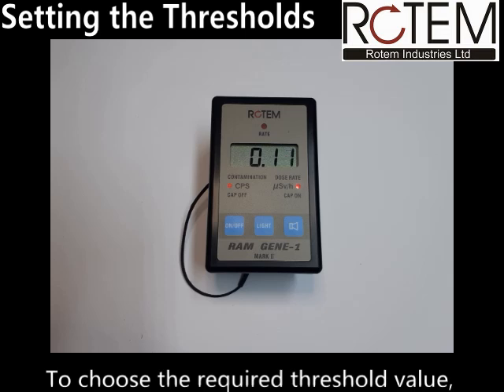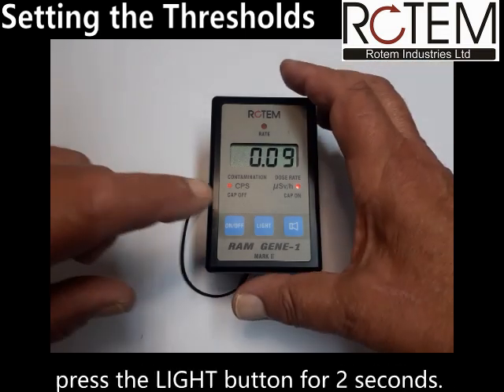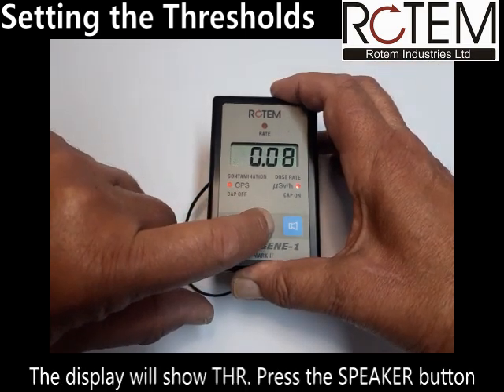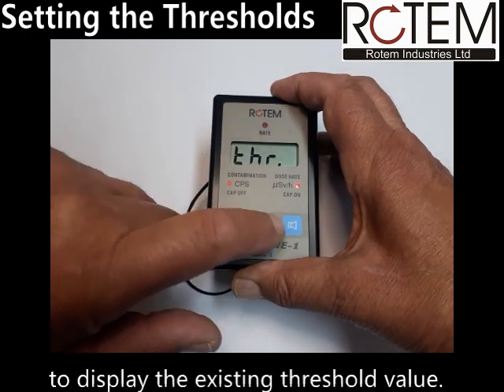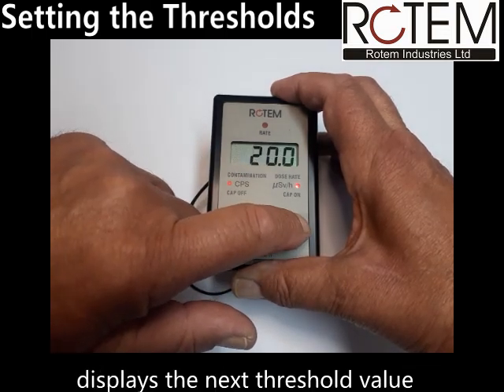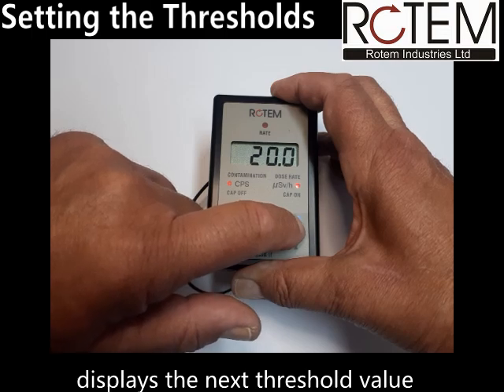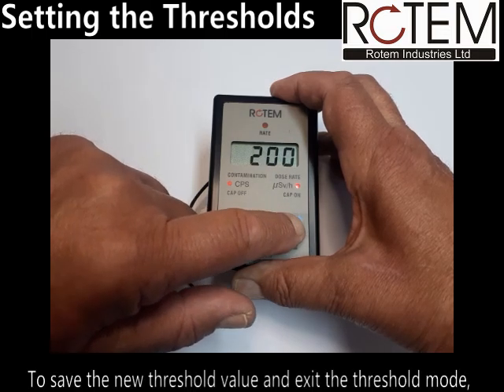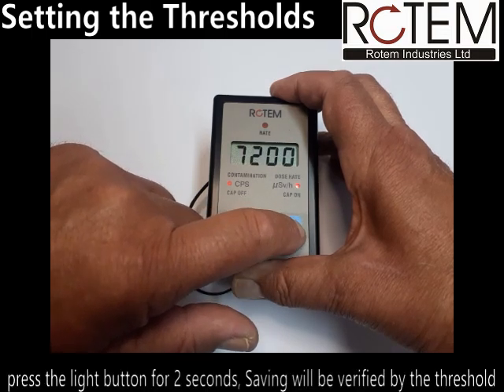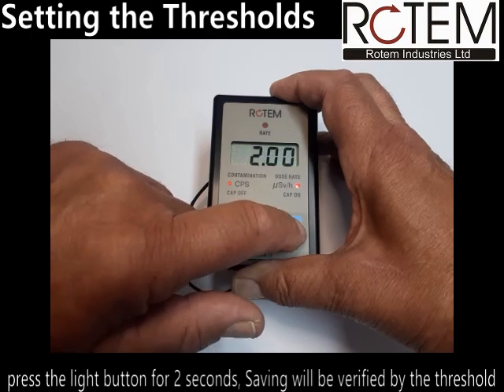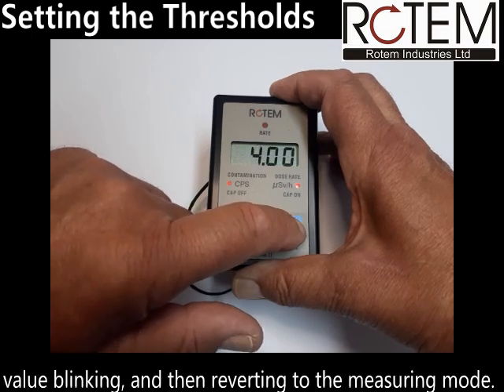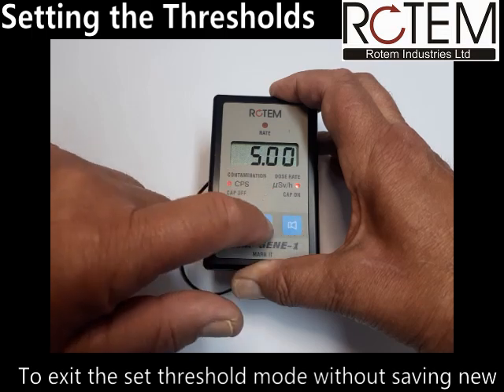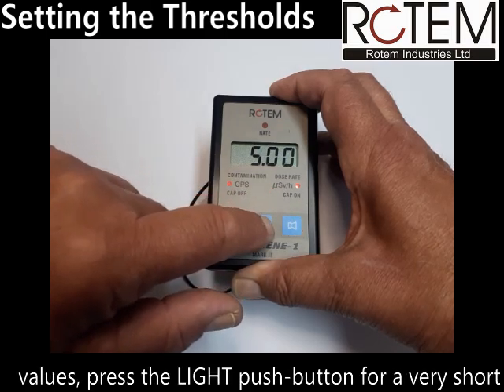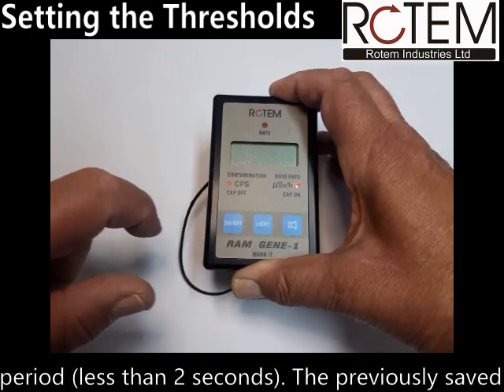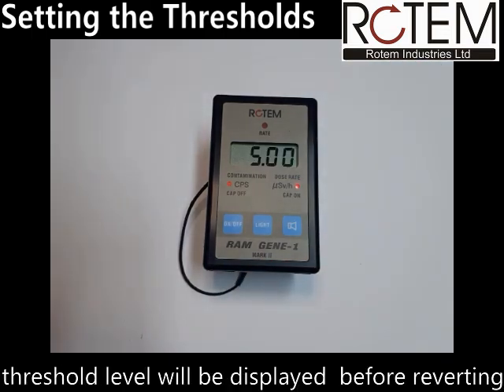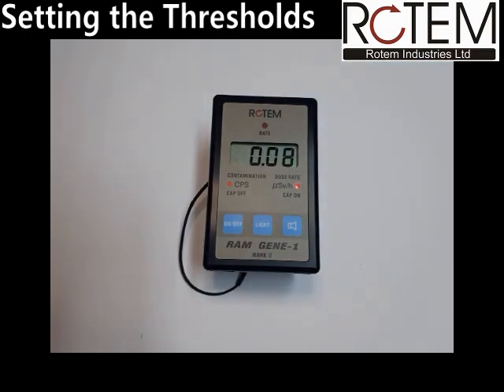To choose the required threshold value, press the light button for 2 seconds. The display will show THR. Press the speaker button to display the existing threshold value. Each additional press on the speaker push button displays the next threshold value. To save the new threshold value and exit the threshold mode, press the light button for 2 seconds. Saving will be verified by the threshold value blinking, and then reverting to the measuring mode. To exit the set threshold mode without saving new values, press the light push button for a very short period, less than 2 seconds. The previously saved threshold level will be displayed before reverting to the measuring mode.